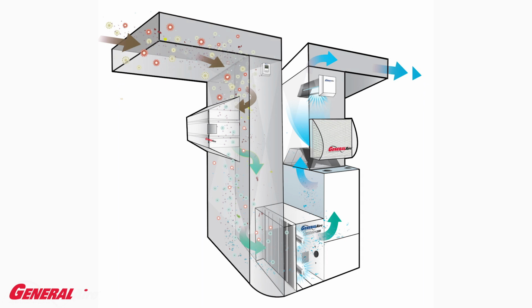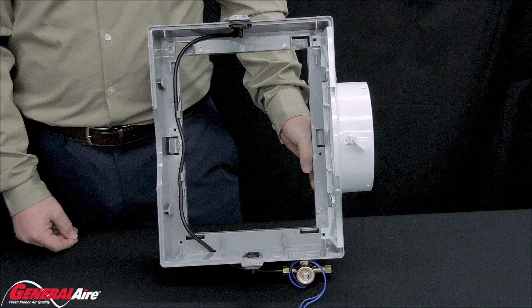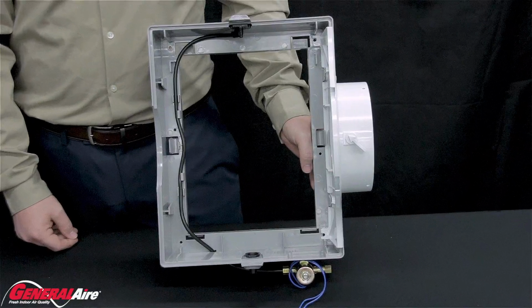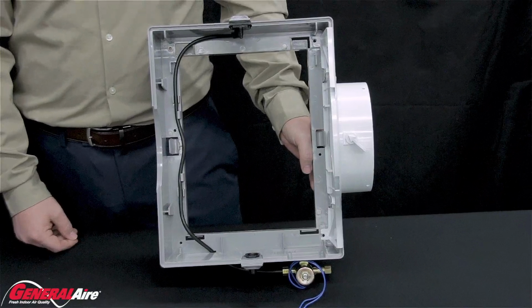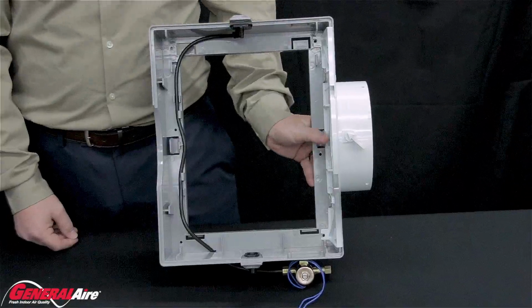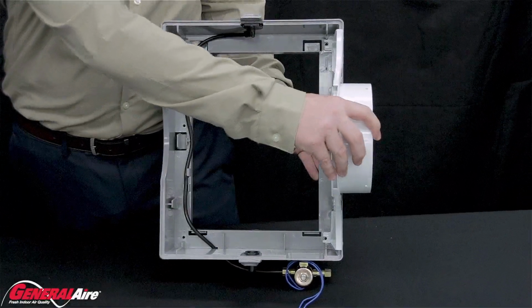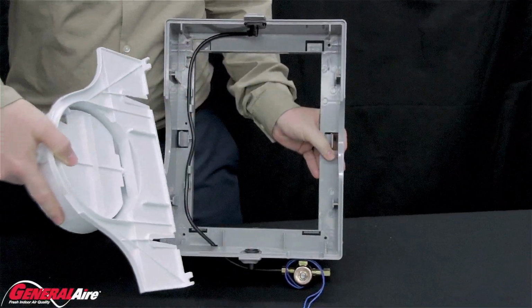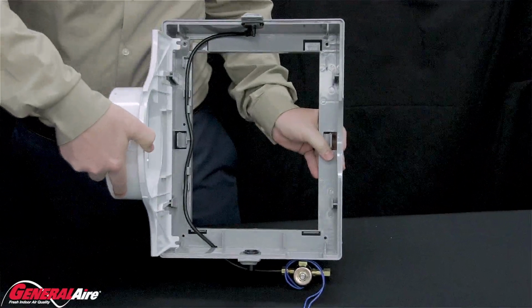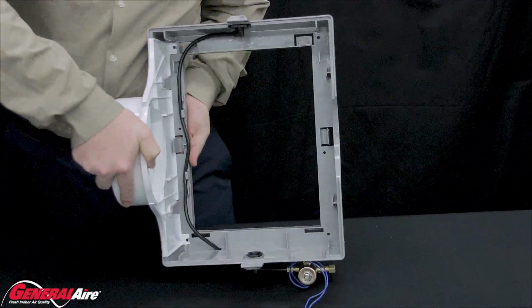Start your installation by deciding whether you want to install it on the supply ductwork, the plenum, or the return ductwork. This decision depends how much room you have for your installation. A unique benefit of the GeneralAire Elite humidifiers is the ability to change and install the bypass from the left to right side. Just pull the tab on the base, and the bypass damper assembly easily lifts away. Simply insert on other side.